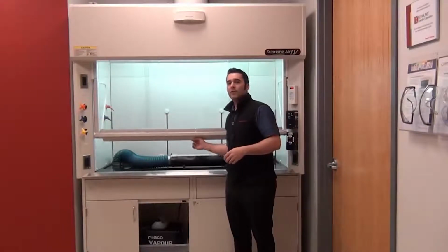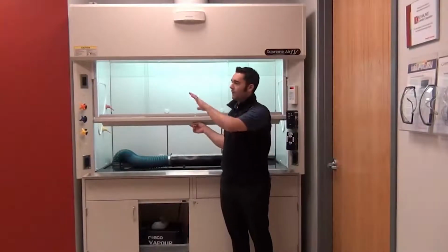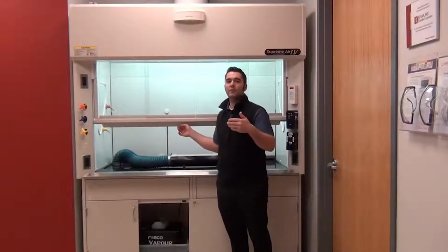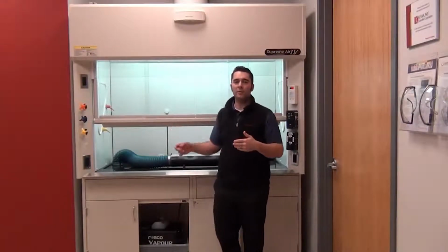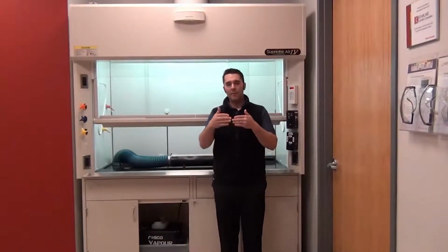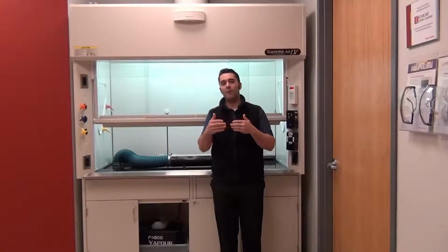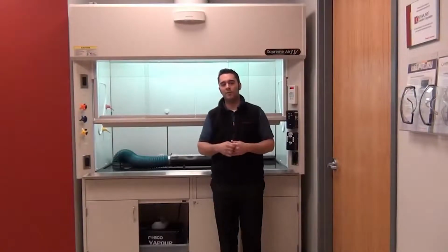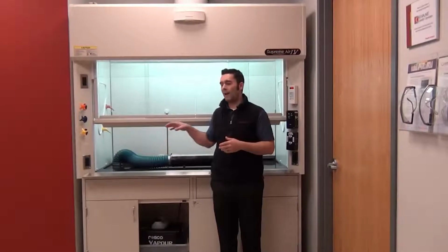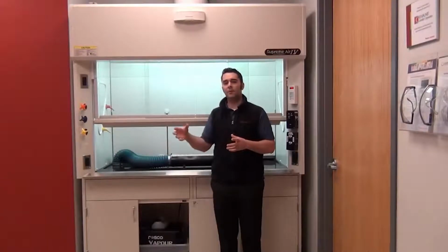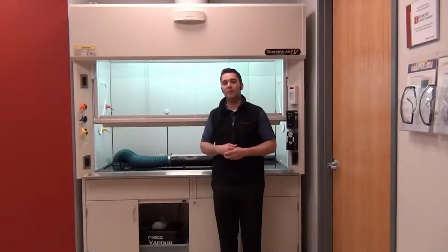So if I'm moving this sash up and down, my other fume hoods that are inside of the space are also going to be automatically reacting to the pressure changes in the ductwork by having the cone inside of the valve automatically change based on the pressure fluctuations. That's going to guarantee not only that I'm going to give you an accurate airflow at all times, but it's going to guarantee that I don't have to have my valve measuring the change for the velocity or the pressure in the ductwork and readjusting its position to guarantee accurate and stable airflow.